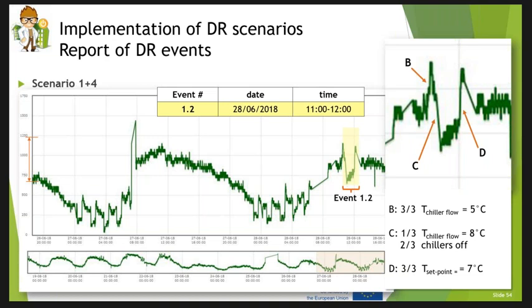So what we did was pre-cool the water of the hydronic circuit of the hospital a little bit. We switched the set point of the chillers from what was the normal set point, 7 degrees, to 5 degrees, and we raised that set point when the event started. So we put it on 8 degrees. That is point C, displayed on the right image.